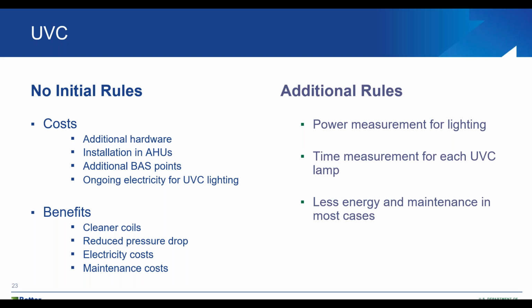UVC. So there's been a lot of talk about adding UVC systems. Some add them to the air handling units, some add them to the spaces themselves. It's not a new technology, it's been around for quite a while. But you need to add hardware, you had to install it, there are additional BAS points that are required, and there's an ongoing electricity cost for operating the UVC.